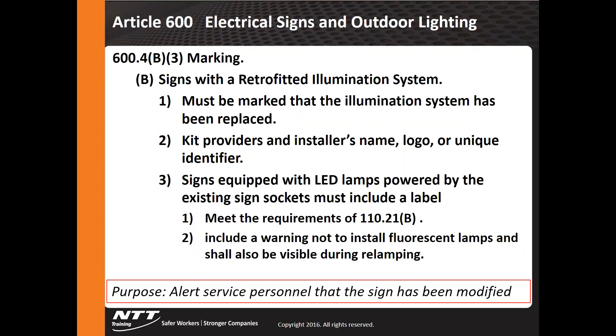Article 600 addresses marking of equipment. As equipment moves from fluorescent to LED, the internal components change and personnel may not realize it. When retrofitting an illumination system with LED tubular replacements into a fluorescent fixture, it must be labeled indicating it has been changed, identifying who provided the retrofit kit. This labeling helps personnel understand the hazards and differences in the system.